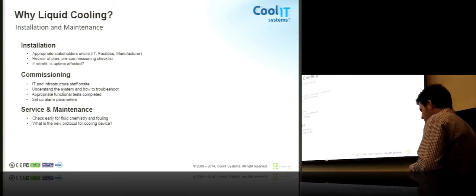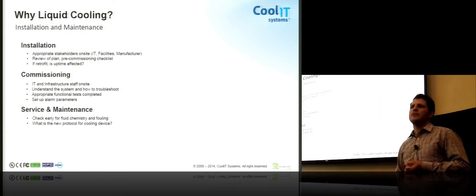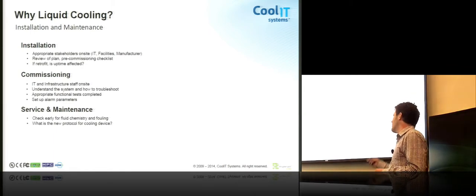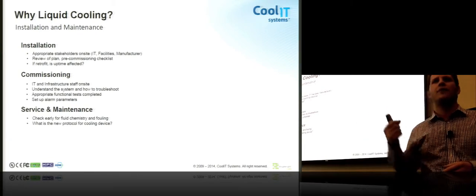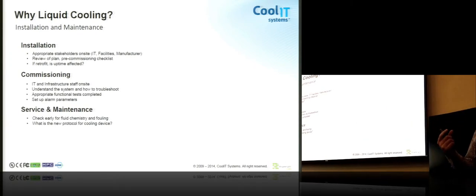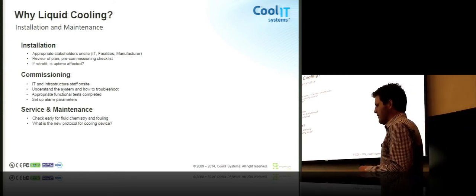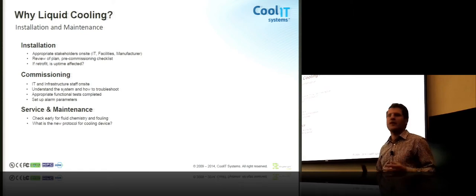Service and maintenance. CoolIT does, in the first year, 3-month, 6-month, and 12-month checks. The first checks are really not for our hardware itself. It's to check for fouling. So we're checking the fluid chemistry. So we'll draw off a little bit of coolant. We'll send it to the lab. And if need be, at that point, we put a little bit of coolant back in. I think the same should be expected for most liquid cooling groups. And as far as I understand, they all do have that capability.